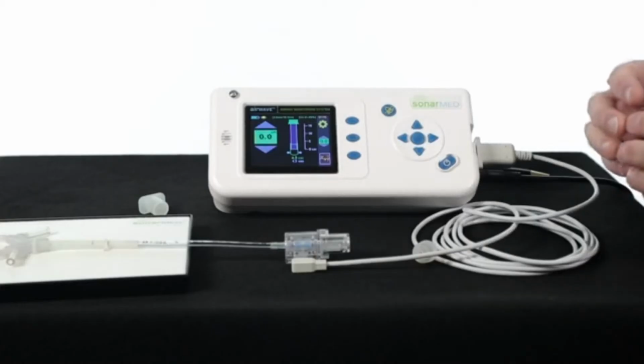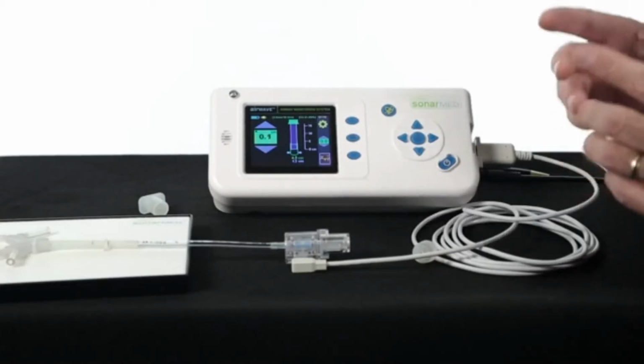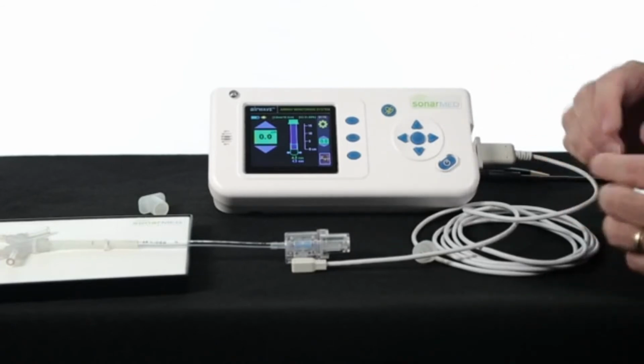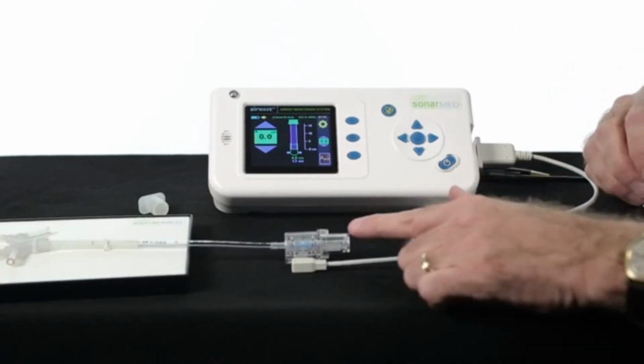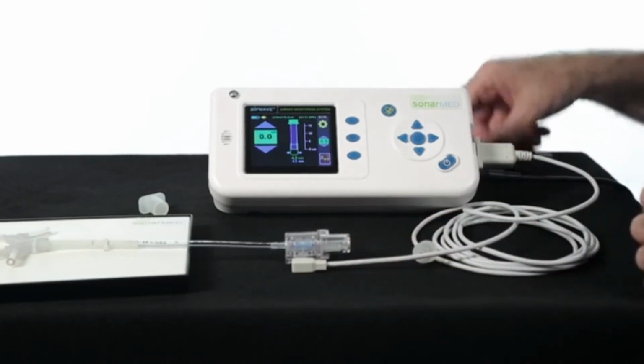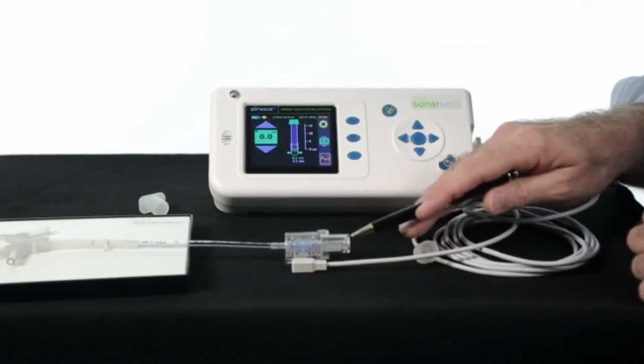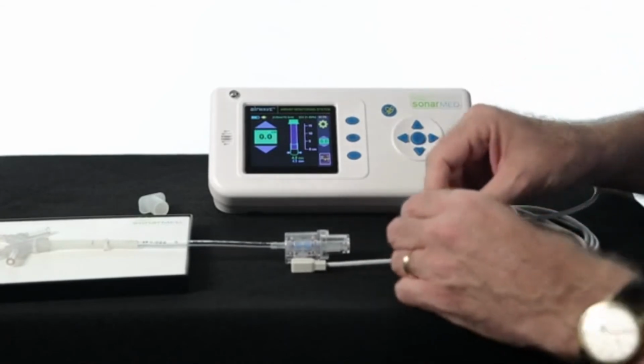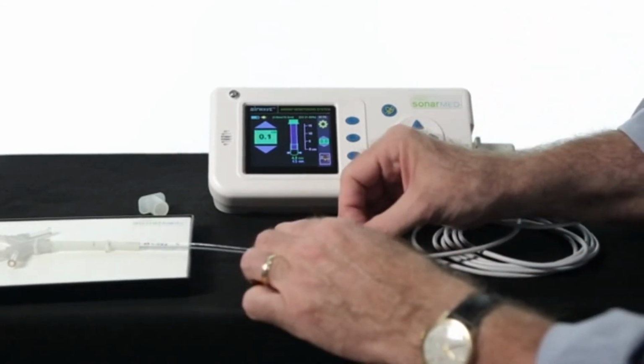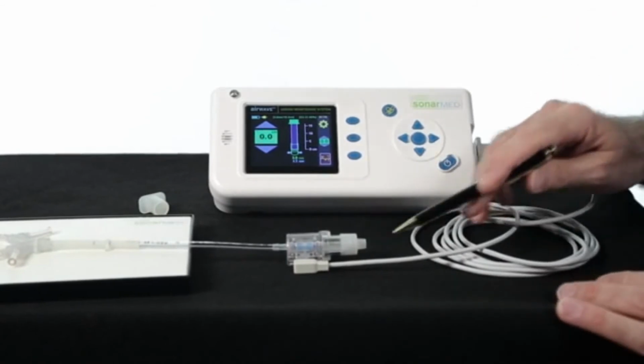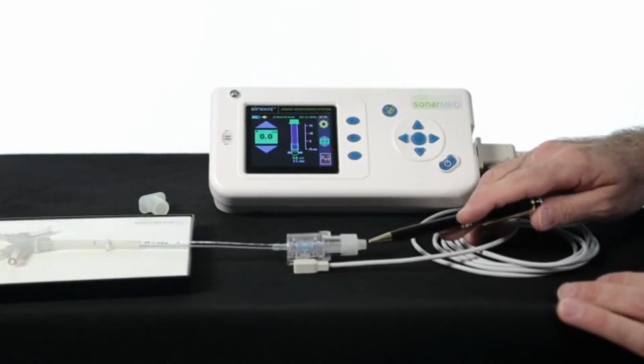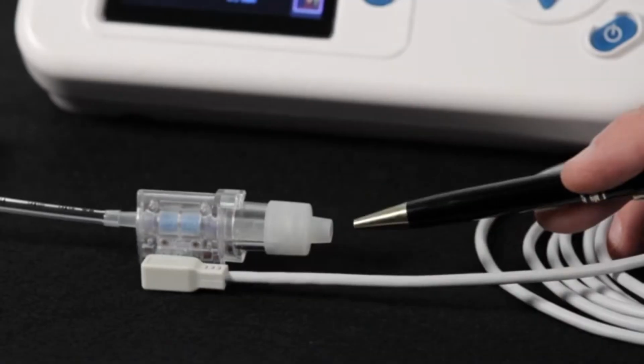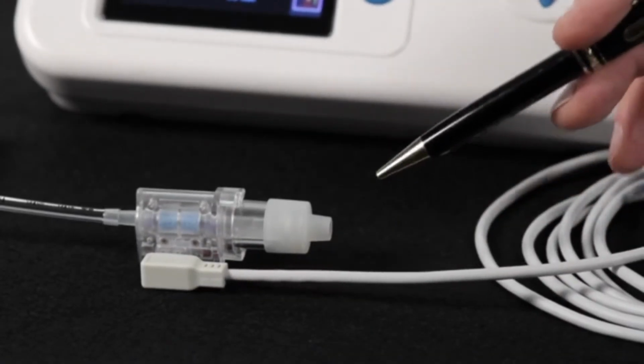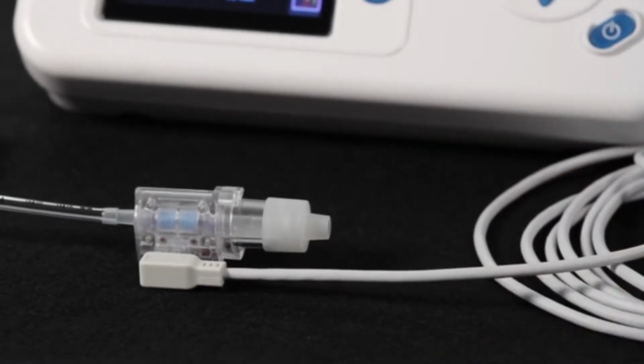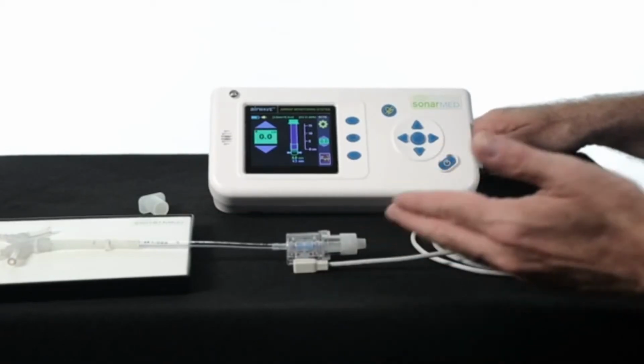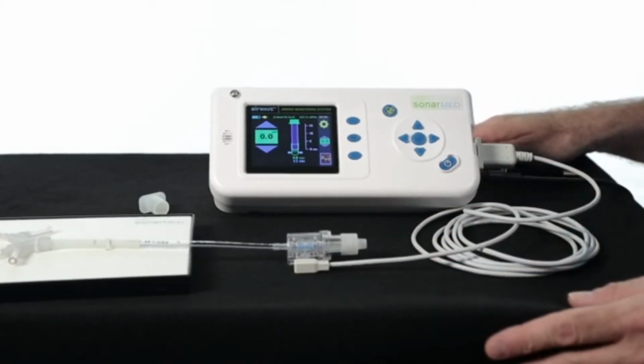In some instances, you may want to connect things to the sensor other than the ventilator circuit. Obviously, the back end of the sensor is designed so that the ventilator circuit can be connected right here. We also have an adapter that can be added to the proximal end of the sensor that will allow an elbow or a Y adapter to be connected right here, so inline suction can be added, and then as you finish the rest of the circuit, be it flow sensors or end-tidal CO2 sensors, they could all be added on the back end of the sensor.